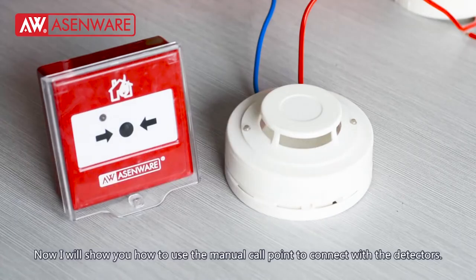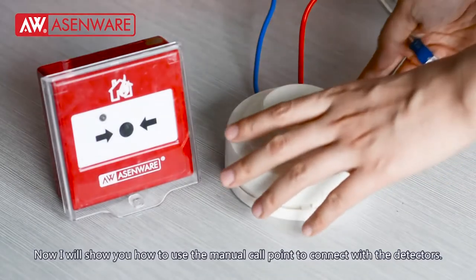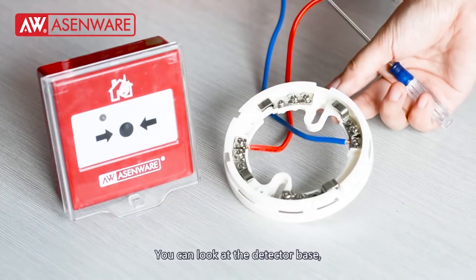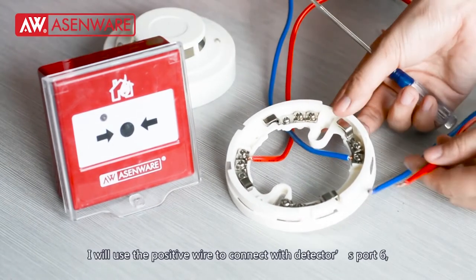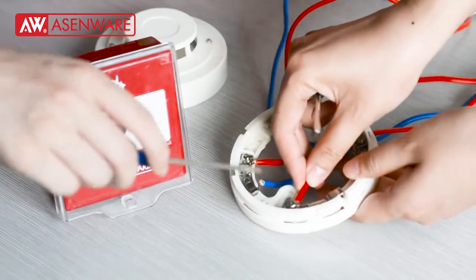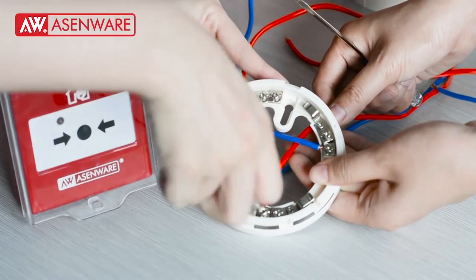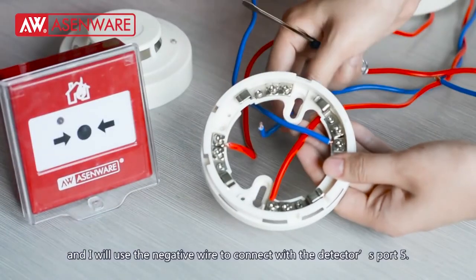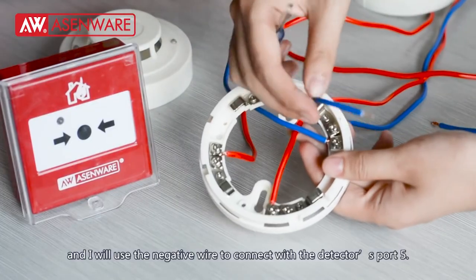Now I will show the third method: how to connect the manual call point with the detector. You can look at the detector base. I will use the positive wire to connect with the detector's port 6, and the negative wire to connect with the detector's port 5.